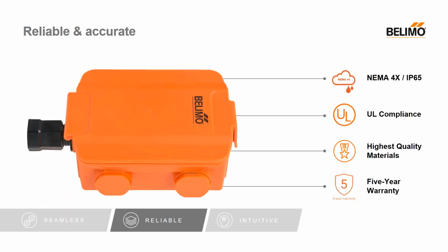Of course, everything is reliable and accurate. When it comes to the resistive sensing side, our NTC temperature sensors have an accuracy of plus or minus 0.3 degrees Fahrenheit. All of our humidity sensors are plus or minus 2% accuracy. When it comes to our CO2 sensors, it's either going to be plus or minus 50 parts per million or 3% of the total reading accuracy. The absolute water pressure sensor we offer is plus or minus 0.5% of the full scale of the measured range. Our water DP is plus or minus 1% of the measured range.